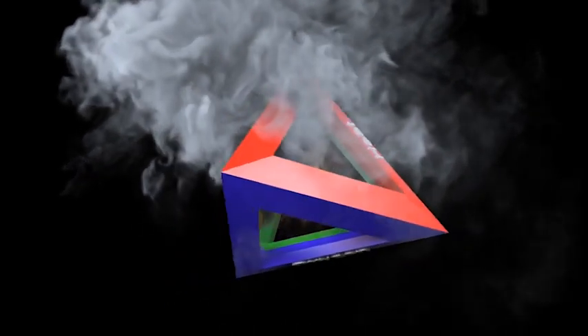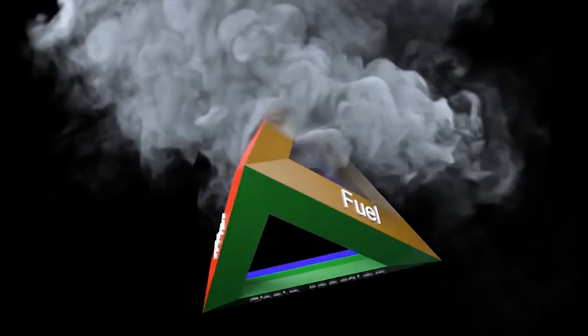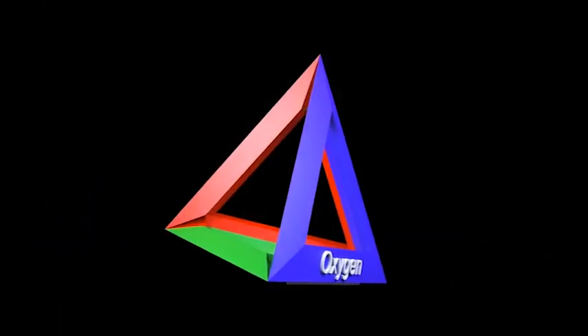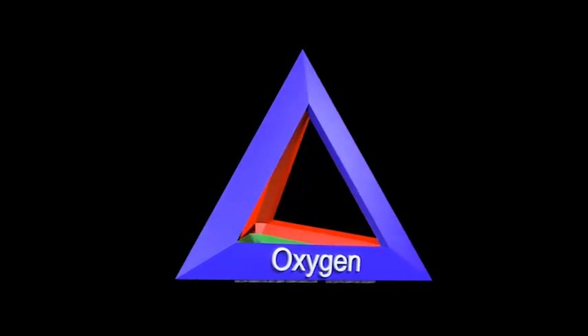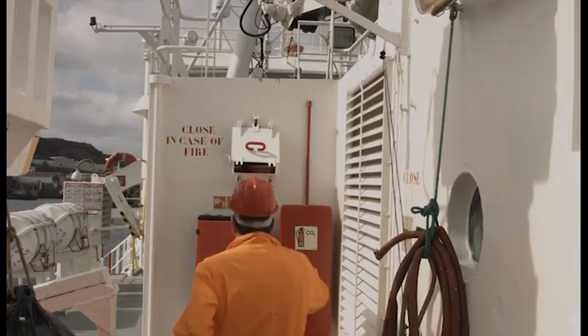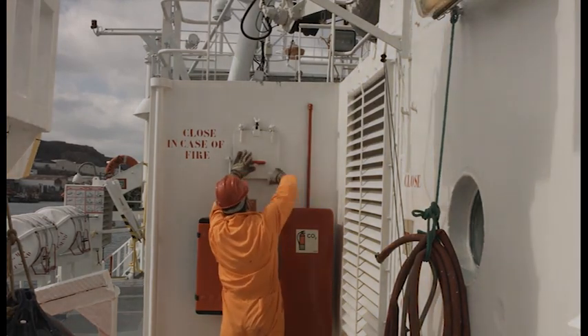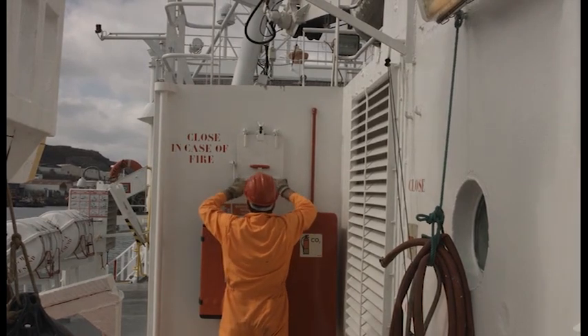The principle of fire prevention is to stop all four elements coming together, whereas the technique of firefighting removes one or more elements from a fire that has already started. If oil or gas is burning from a broken pipe, simply shutting off the gas supply stops the fire. On a vessel, remote closing valves can be used to shut off the supply of burning fuel. When closed, fire dampers and vent flaps starve a fire of oxygen.